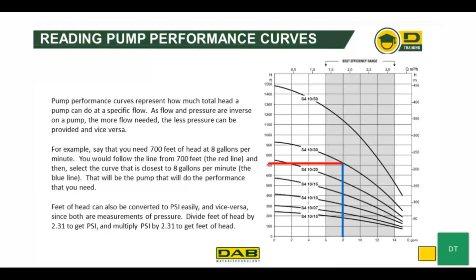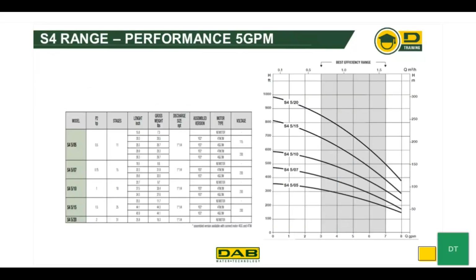Feet of head can also be converted to PSI easily and vice versa, since both are measurements of pressure. You divide the feet of head by 2.31 to get the PSI, and you multiply PSI by 2.31 to get feet of head. We can see that this is the curve and the characteristics for the 5 gallons per minute S4 range.